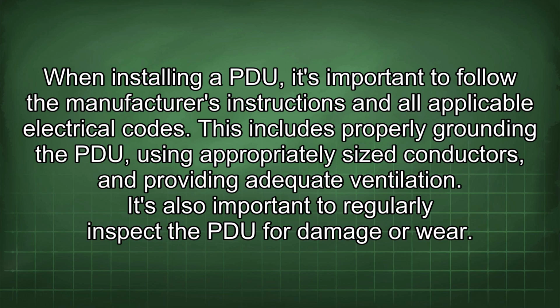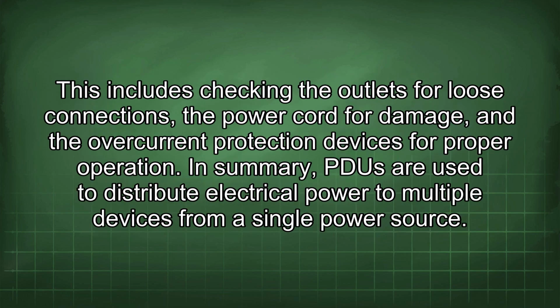This includes properly grounding the PDU, using appropriately sized conductors, and providing adequate ventilation. It's also important to regularly inspect the PDU for damage or wear. This includes checking the outlets for loose connections, the power cord for damage, and the overcurrent protection devices for proper operation. In summary, PDUs are used to distribute electrical power to multiple devices from a single power source.